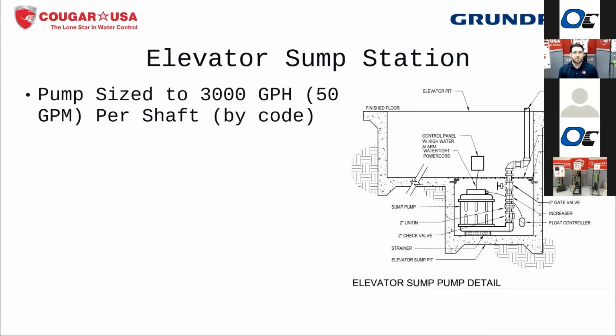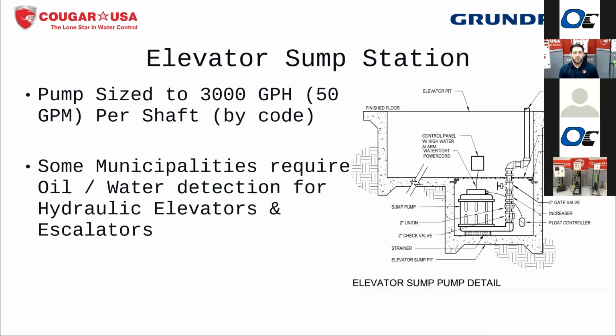Okay, elevator stations, just touch on this real quick. We have the requirement for the 50 GPM per elevator shaft now, and I really just want to highlight that is driving some of our elevator sump pumps to be bigger than they used to. And now it's causing us to plan for motor controls when we have to have 3-phase pumps. And so you're going to have to plan to have that motor control panel somewhere nearby the elevator pit itself, as well as having to address any oil and water detection requirements in the local municipality.